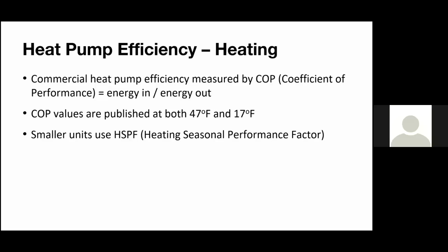And then we look at smaller units. So this is talking about our mini split units, so either a one-to-one connection or a multi-split unit. But for heating, we're using HSPF, which is our heating seasonal performance factor. So basically, this is very similar to IEER in the sense that it is looking at multiple data points in the heating season, basically throughout the whole heating season. You're only going to be really using this for mini splits. Anything above 65,000 BTUs, this is not going to apply. You're going to be bumping up to COP, just like you would SEER.